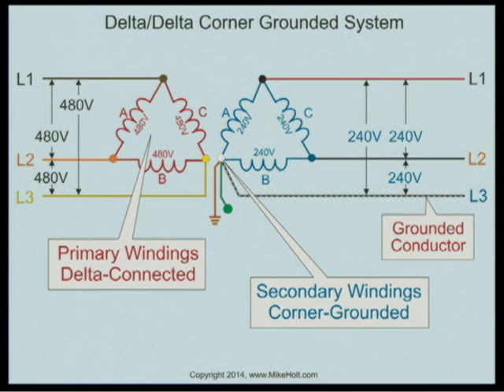This is not something that's very common. It's mostly used in old industrial applications in Chicago, New York and Philadelphia warehouse areas. Let's assume that the secondary in this case could be 240-volt line to line or 480-volt line to line. That's not important. You take the delta system and you ground one corner. That means this is a corner grounded system. That means the conductor leaving that, we wouldn't even call this line 3. We would call this a grounded conductor. But it's still a third phase.